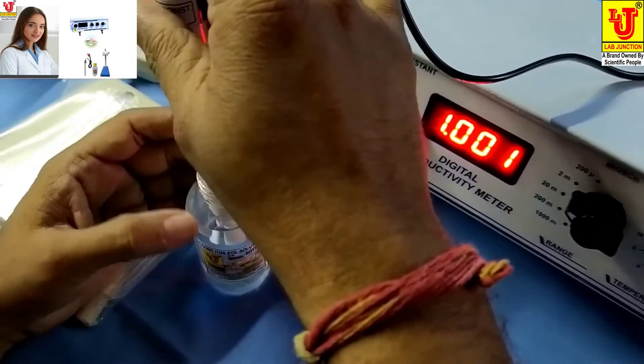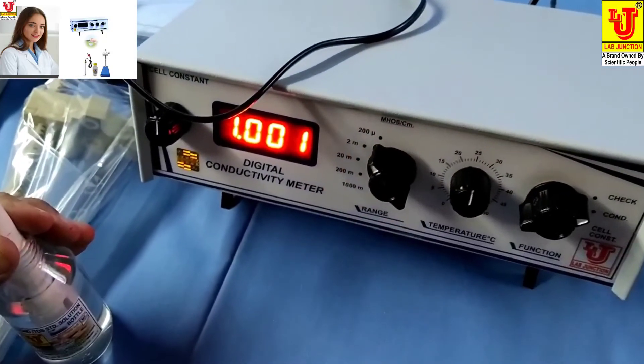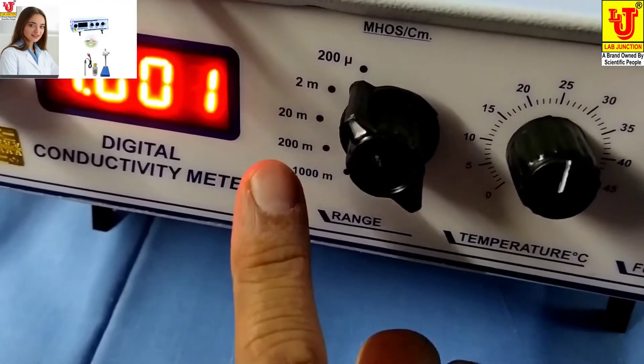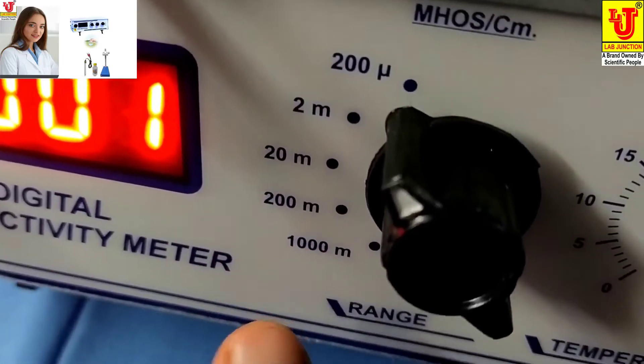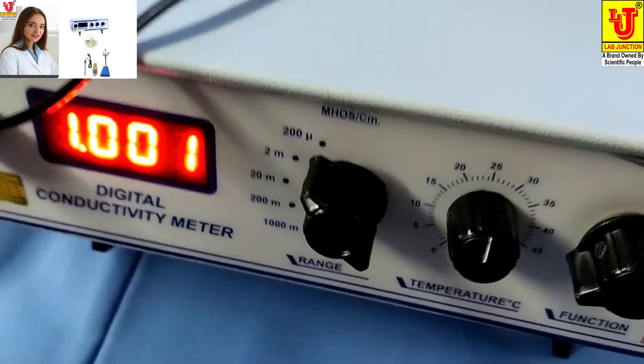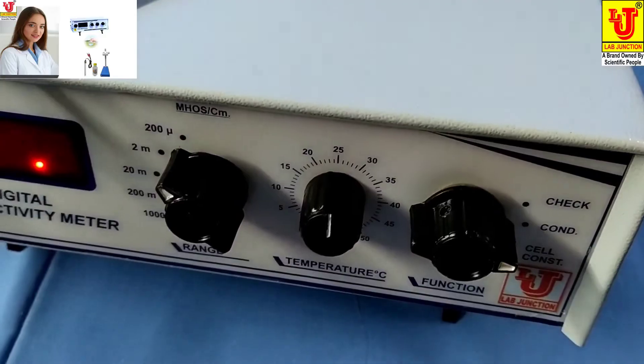You can dip it in. The range settings are: first range 200 microsiemens, second is 2 milli, third is 20 milli, fourth is 200 milli, fifth is 1000 millisiemens. Now you can set it to conductivity position.